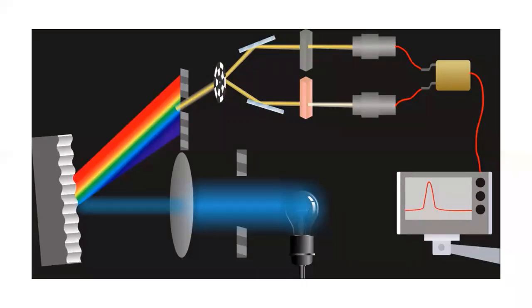The last detector is the charge-coupled device, which is called CCD. This is similar to the diode array detector. Instead of photodiodes, you have photocapacitors. In every photocapacitor, there are detector elements, and there are thousands to millions of photocapacitor elements in a CCD. Just as with the other detectors, the photocapacitors convert photons into electrons or electrical energy.